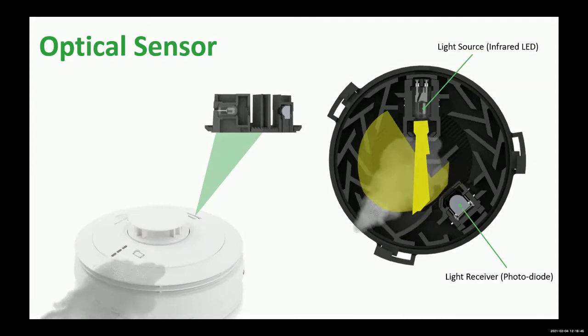We're looking for obscuration levels. So we want the beam to be obscured at a certain level. Under the standards, we have to manufacture the device at an obscuration level between 2 and 4%. The device has to activate at that stage.